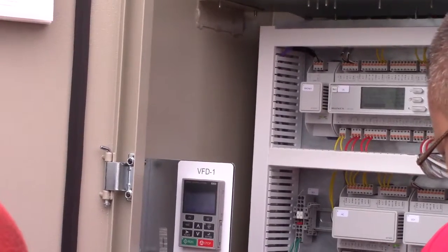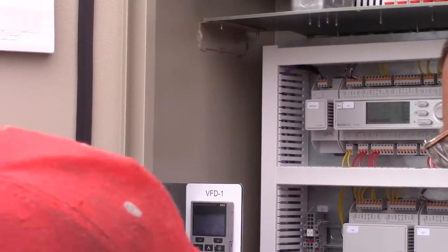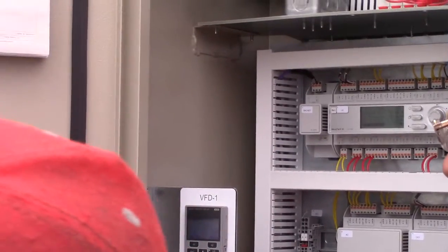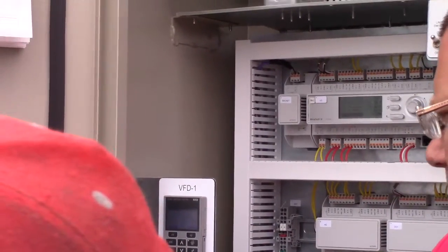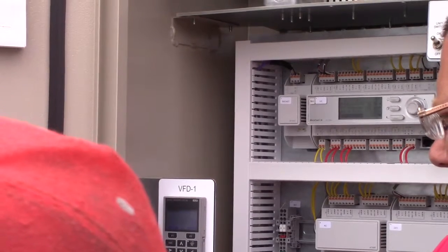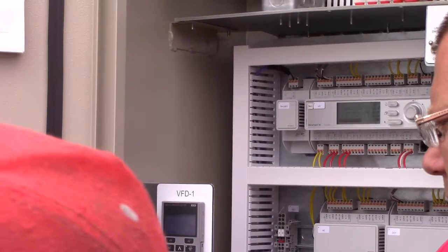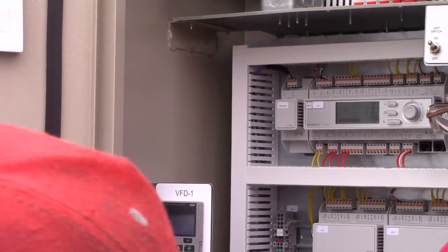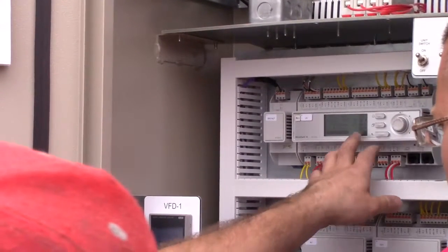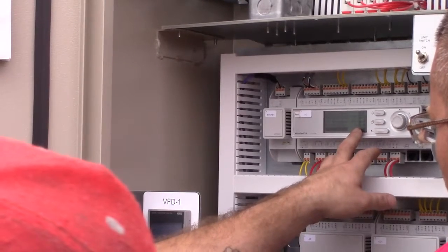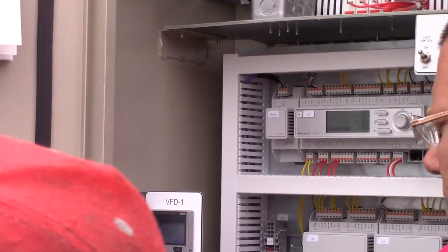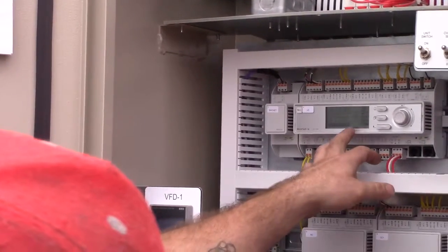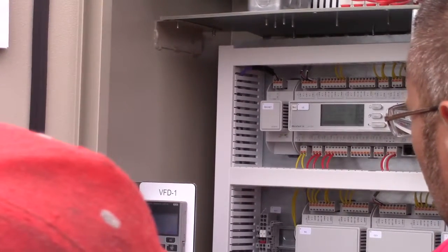But everything that controls the valve system within that compressor used to be a slide system that controlled the staging. That's what we're doing with the drive now. So we do have a couple valves there to do that pressure ratio control of those discharge ports. Those are run on pneumatic oil pressure within that compressor. So if you are not maintaining these oil filters, you could potentially have problems operating that screw properly. So it's a good thing to keep an eye on, on regular maintenance when you're logging your machines.